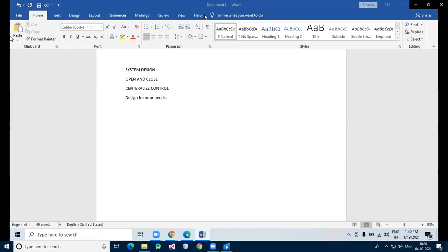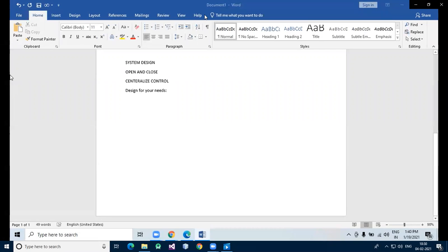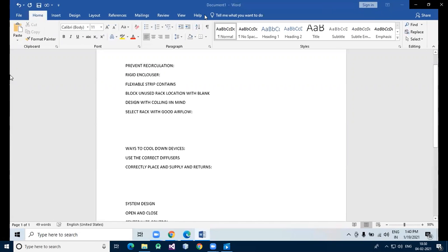Selecting a technology that can scale to future needs is a critical part of your consideration, because if you do add more power to your system, you will need to add more cooling. Most server manufacturers are working on solutions that bring refrigerant based cooling modules into the rack to manage heat of 30 kilowatts and higher. This will make the base system compatible with the next generation of cooling strategies.